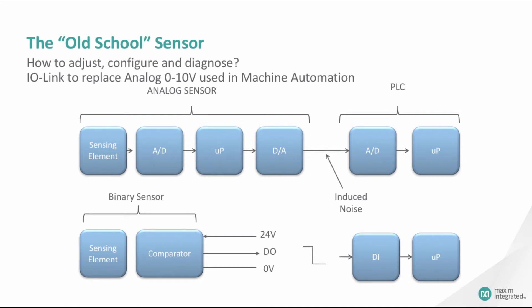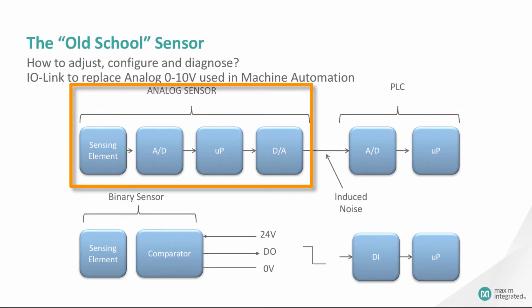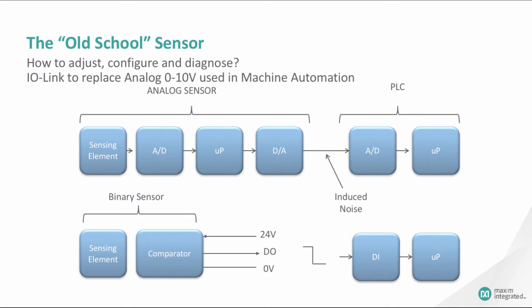Historically, a typical sensor consisted of the sensing element and some way to get the sensing data to a controller. Data was often transferred to the master or controller in analog format and was unidirectional, from the slave to the master only. This added extra steps — note the D-to-A and A-to-D conversions — and added extra cost and footprint. This was also susceptible to noise, limiting the full functionality of the system.